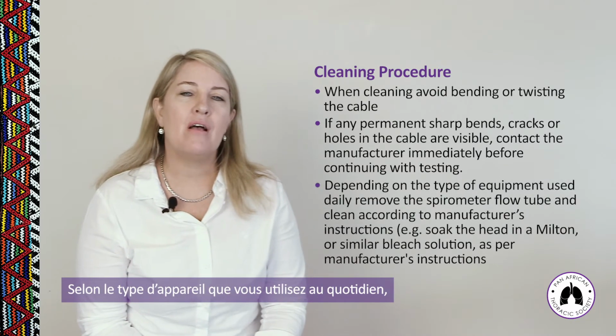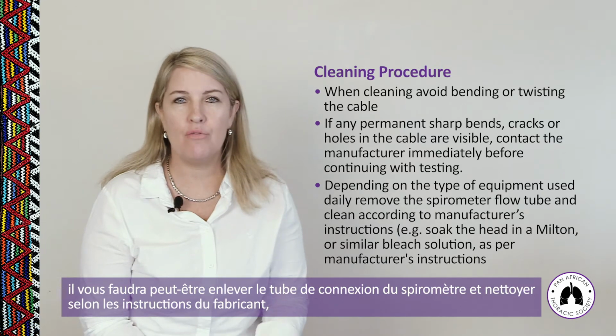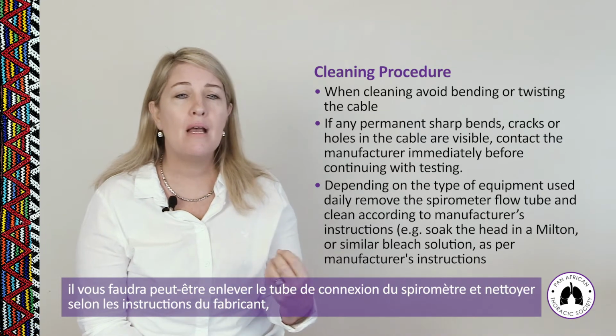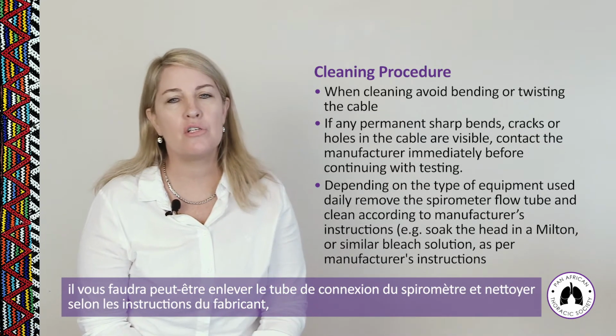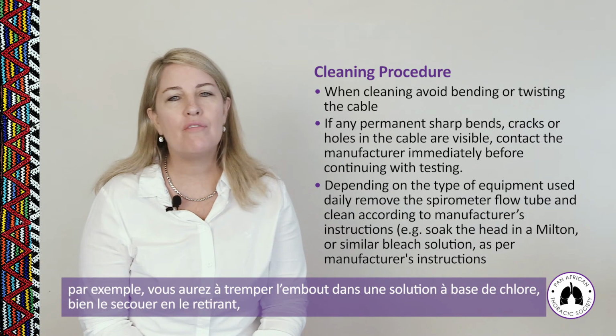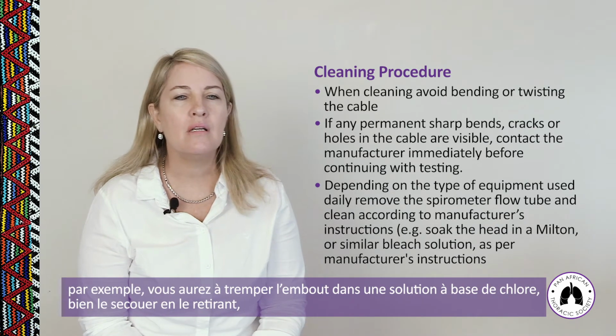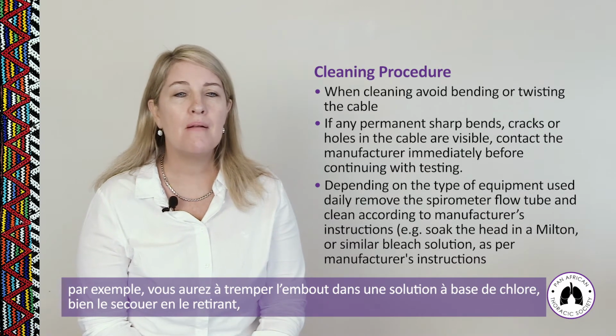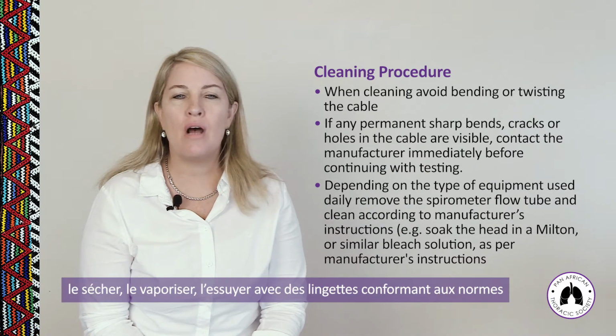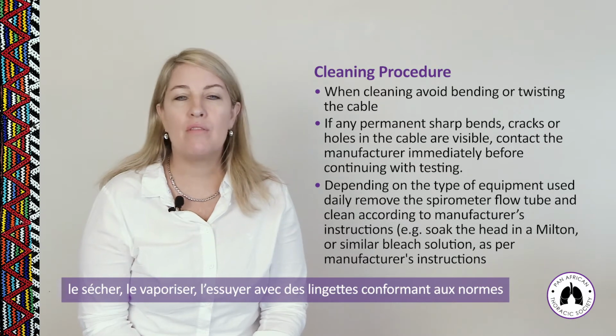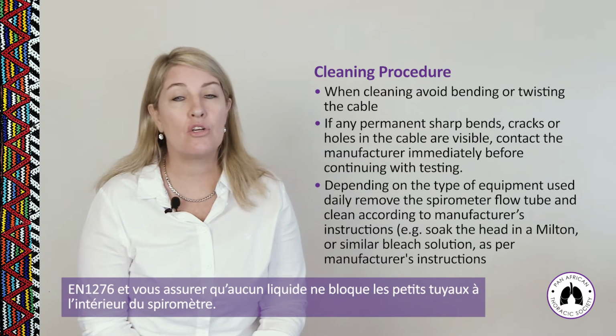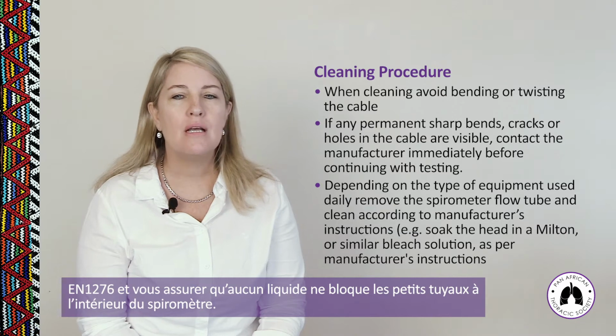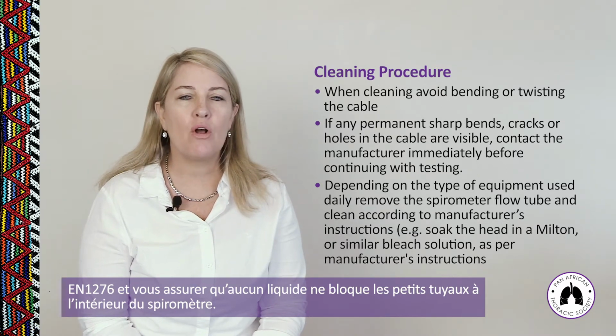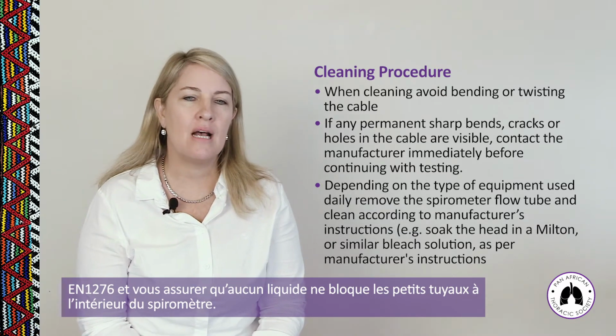Depending on the type of equipment used daily, you might need to remove the spirometer flow tube and clean according to the manufacturer's instructions. You could, for example, soak the head in Milton or a similar bleach solution as per the manufacturer's instructions. Shake the solution out, dry, spray, wipe with EN1276 compliant wipes or solutions, and make sure no liquid is blocking any of the small tubes inside the spirometer.